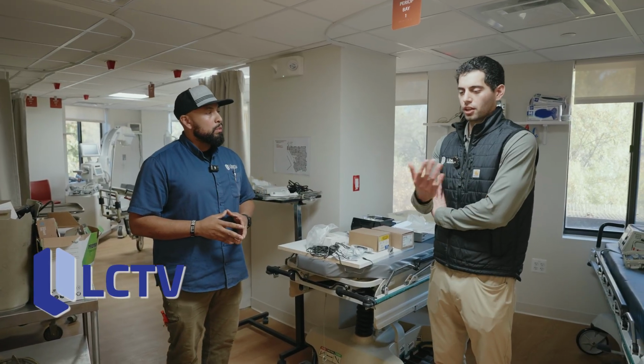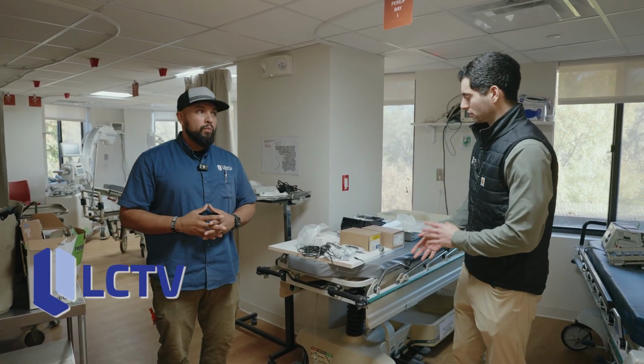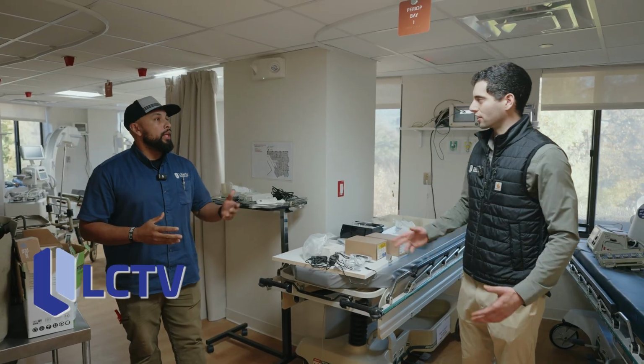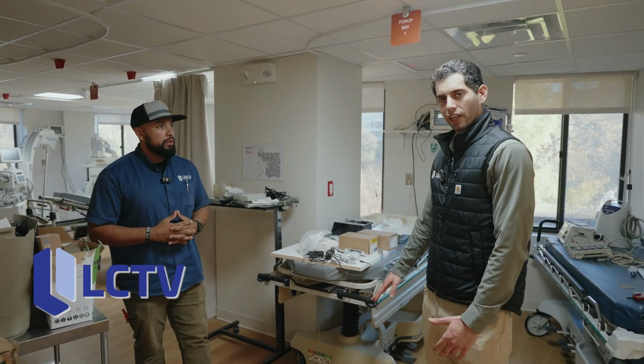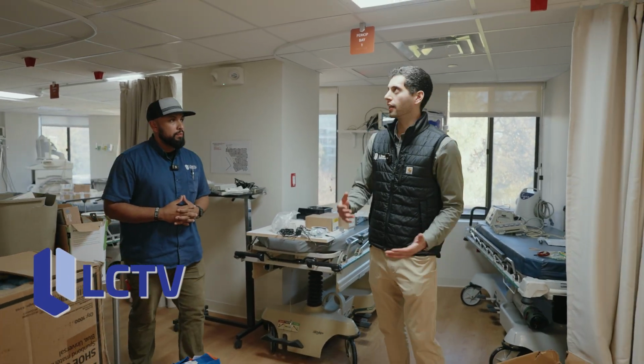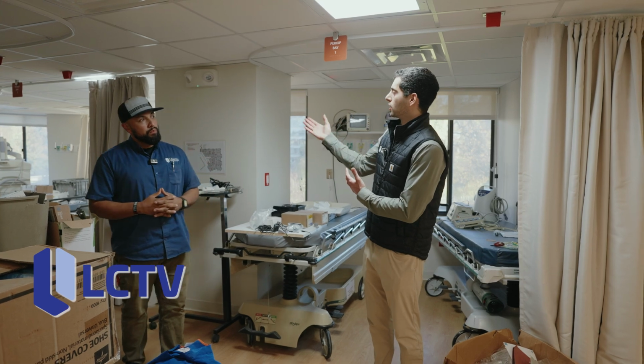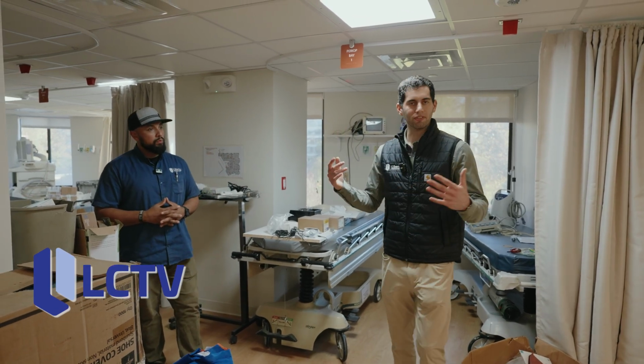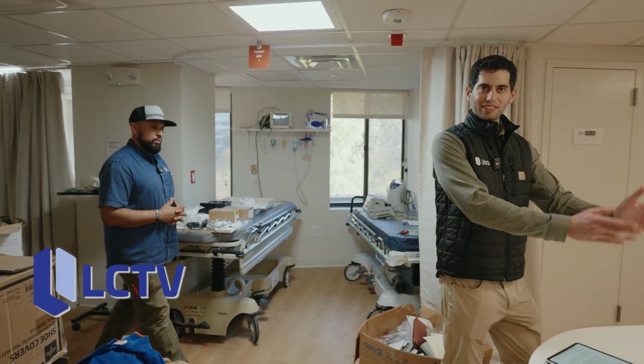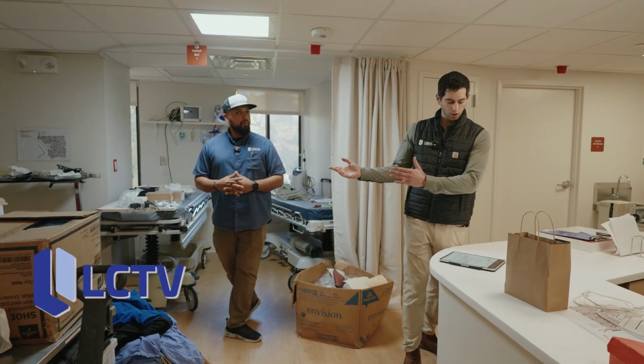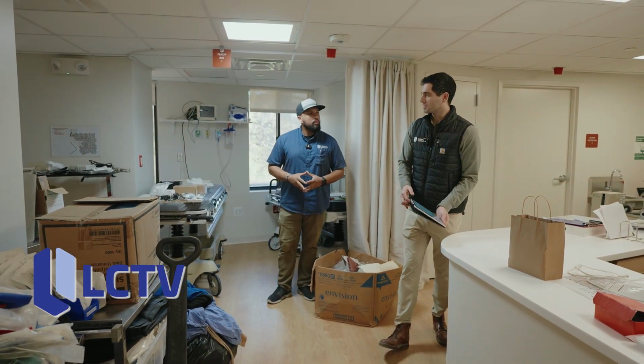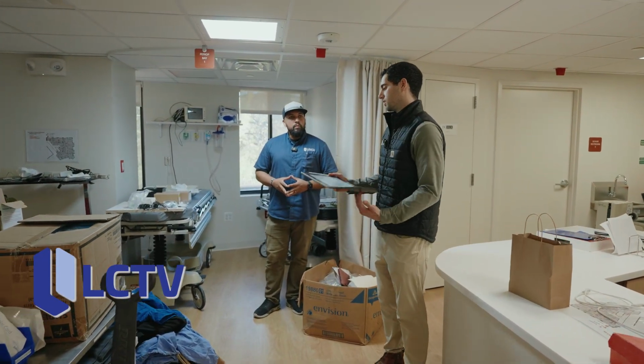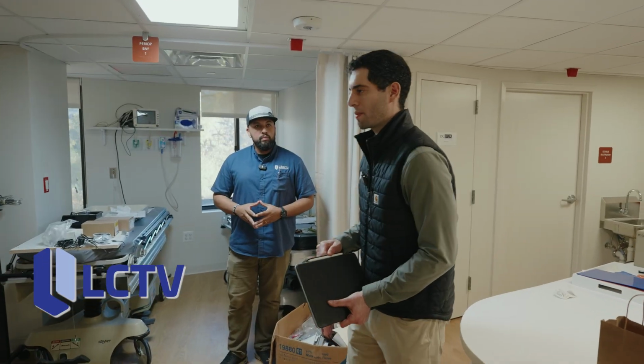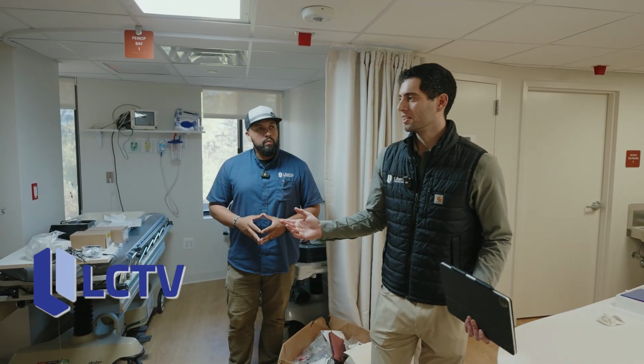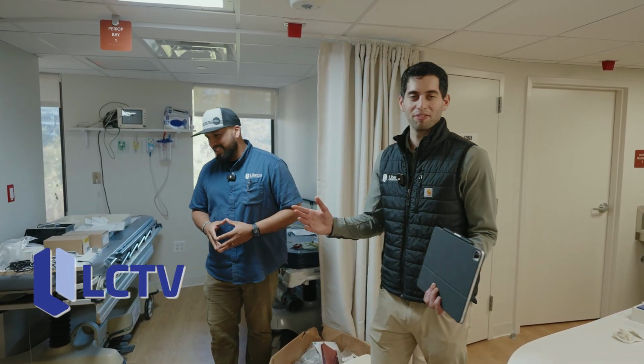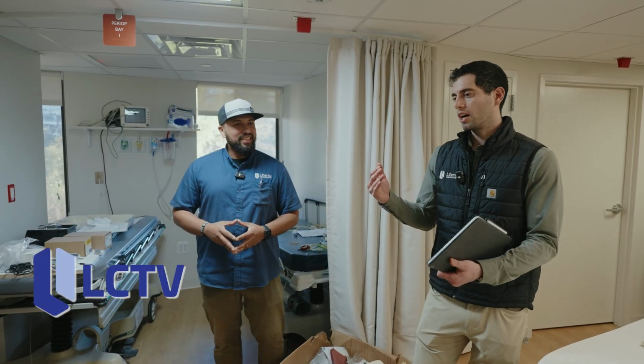You also have to think about where the curtain will go, since there needs to be space between the curtain and the stretcher, not just tight against it. And when you locate the code blue lights, they all have to be visible from wherever the nurse would be sitting. A lot went into this design, but those clearances are like OSHA rules, written in blood. There's a reason they exist, so we try to follow them as closely as possible.